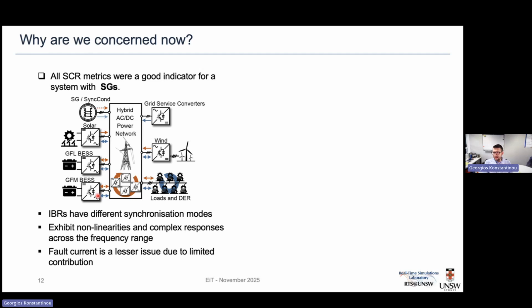Additionally, since we have control functions and the system becomes non-linear, it exhibits very complex responses across the frequency range. So a simple equivalent impedance value no longer describes everything we expect from a power electronics converter, because its behavior changes at low frequencies, at frequencies around the fundamental 50 Hertz, and at much higher frequencies, because of the way the converter operates.